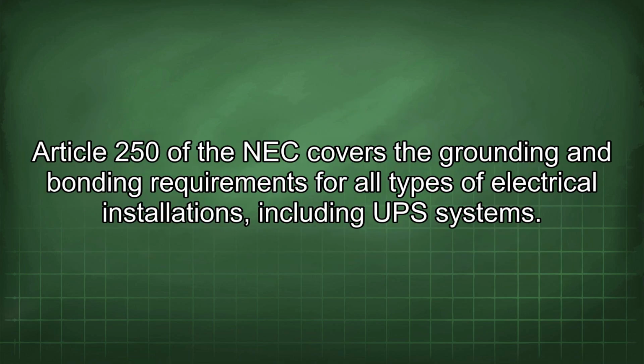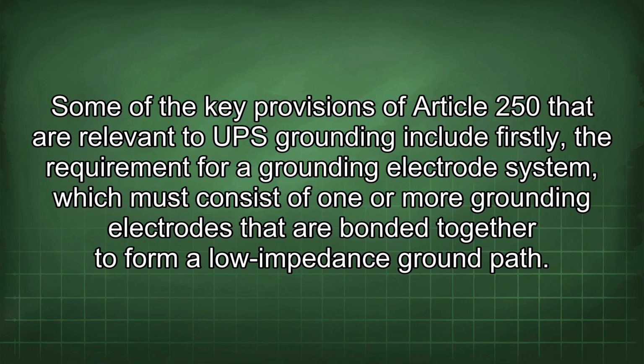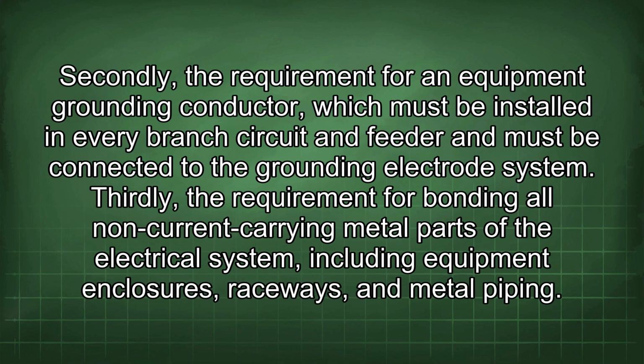Article 250 of the NEC covers the grounding and bonding requirements for all types of electrical installations, including UPS systems. Some of the key provisions of Article 250 that are relevant to UPS grounding include, firstly, the requirement for a grounding electrode system, which must consist of one or more grounding electrodes that are bonded together to form a low-impedance ground path. Secondly, the requirement for an equipment grounding conductor, which must be installed in every branch circuit and feeder and must be connected to the grounding electrode system.